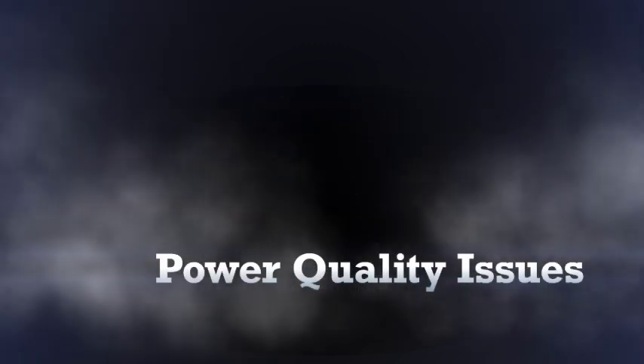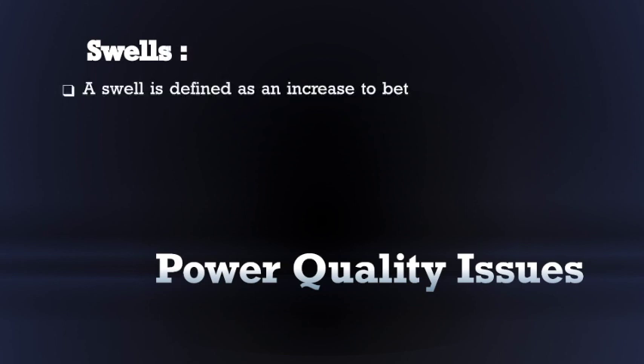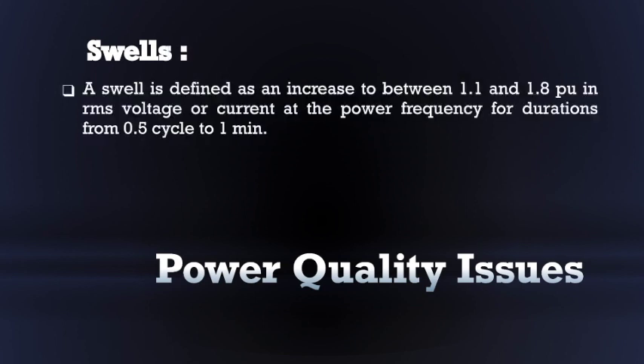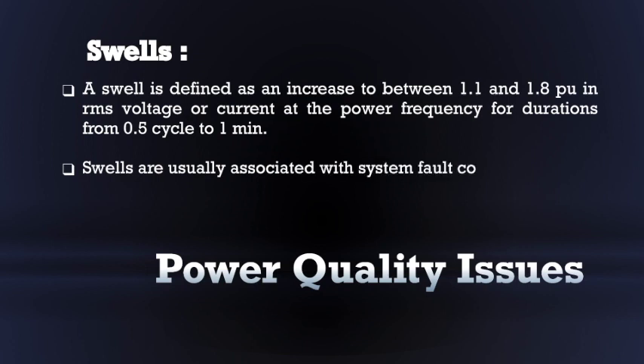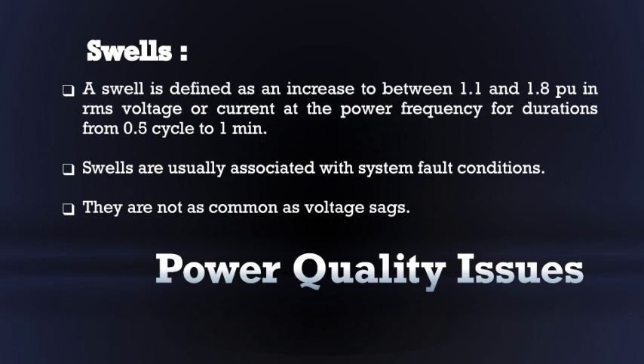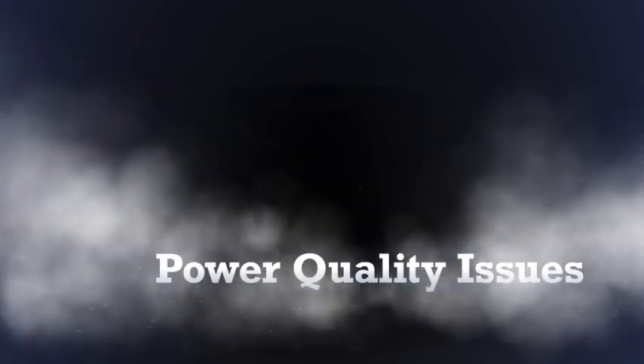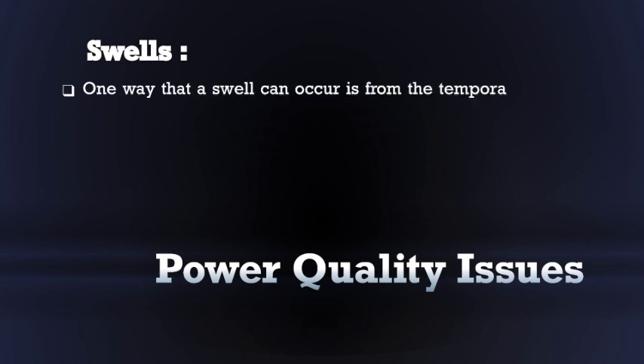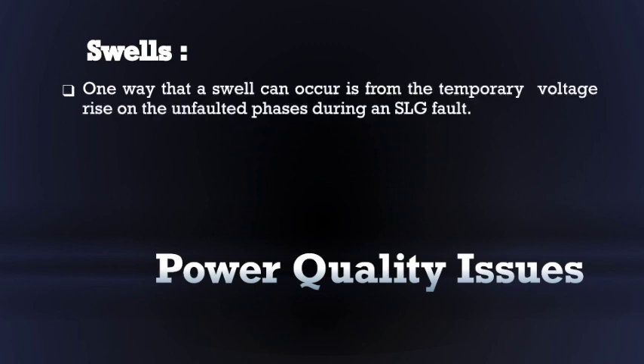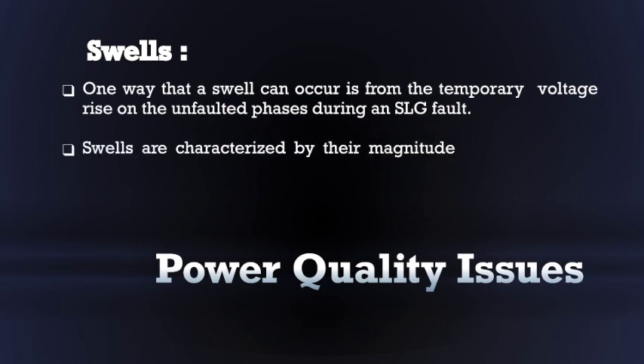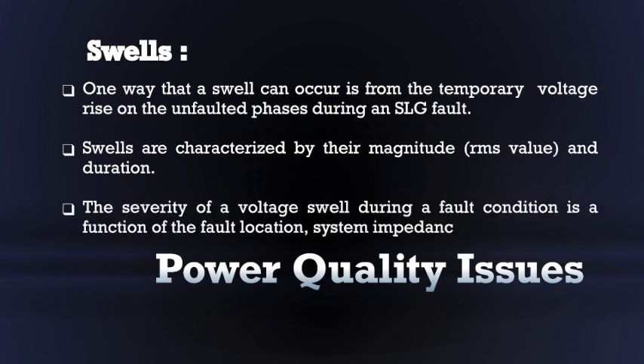A swell is defined as an increase between 1.1 and 1.8 per unit in RMS voltage or current at the power frequency for durations from 0.5 cycle to 1 minute. Swell is exactly the opposite phenomenon of sag. Swells are usually associated with system fault conditions, but they are not as common as voltage sags. One way that a swell can occur is from the temporary voltage rise on the unfaulted phases during a single line to ground fault. Swells are characterized by their magnitude and duration. The severity of a voltage swell during a fault condition is a function of fault location, system impedance, and grounding.